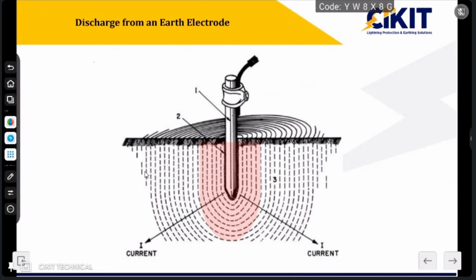So this is what happens during the discharge of fault current. If any fault current is discharging from this earth electrode, the discharge is taking place from the electrode to the surrounding medium. And if you observe closely, the potential which is very near this earth electrode will be very high, and if you move away from the earth electrode, the potential reduces. So the points which are very close to this earth electrode will be of very high potential, and if you move away from this earth electrode, the potential reduces gradually.